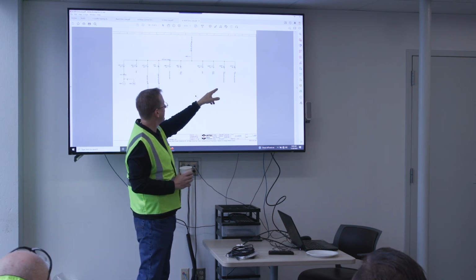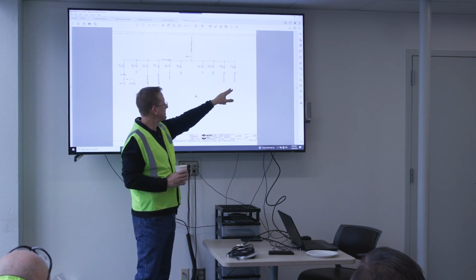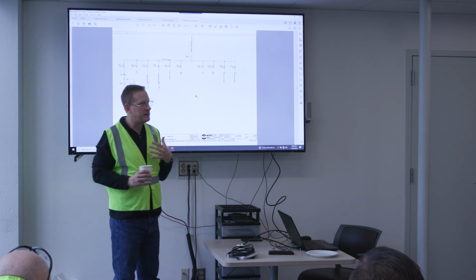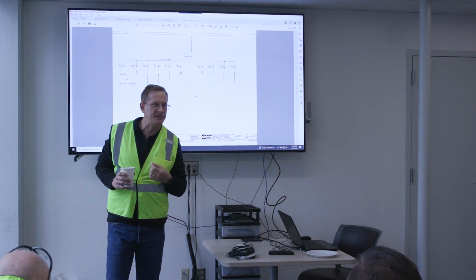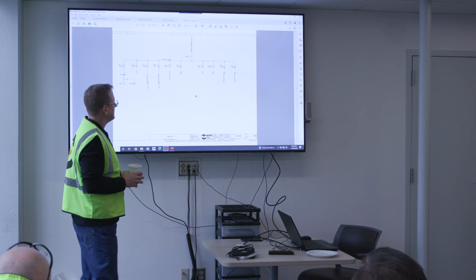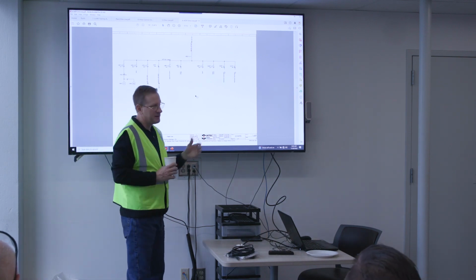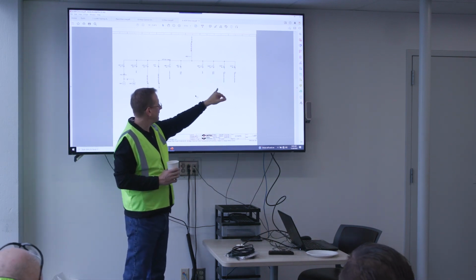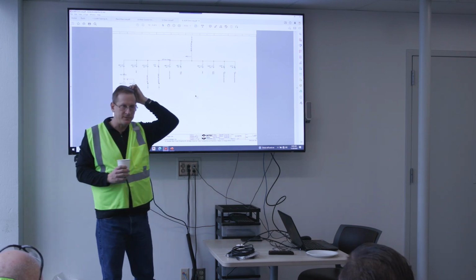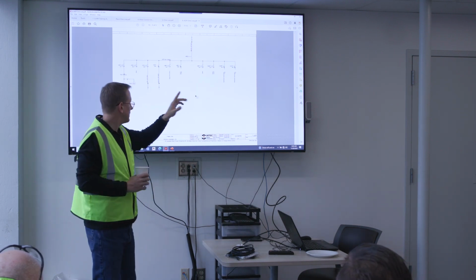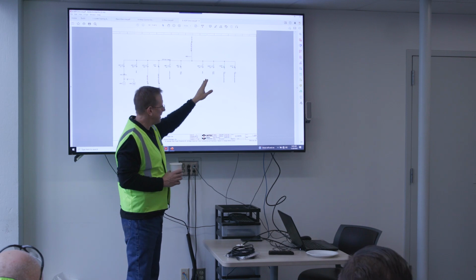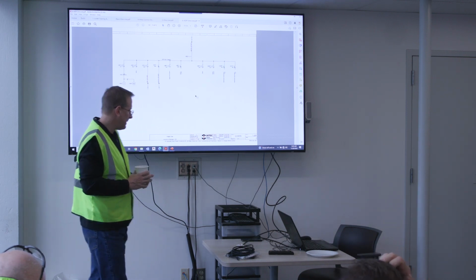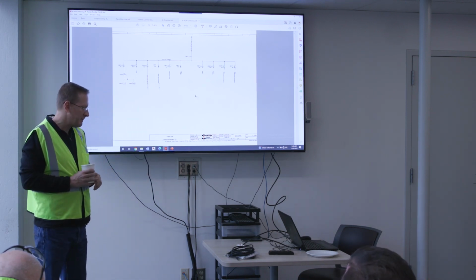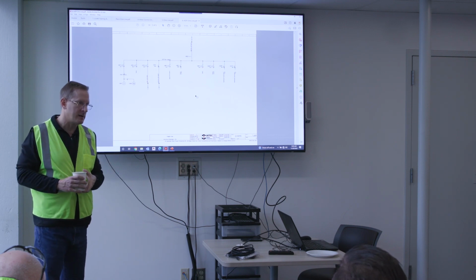Let me go back to that. We've also got some sources, some feeds into what we call the ventilation control panel. So there are a couple of ventilation fans that basically keep the air flowing over the unit. And so we provide the 480 volts for those fans as well. Okay, so that's coming from those two feeds. Back to the DCP. We have a DCP panel that we utilize for medium voltage switchgear.